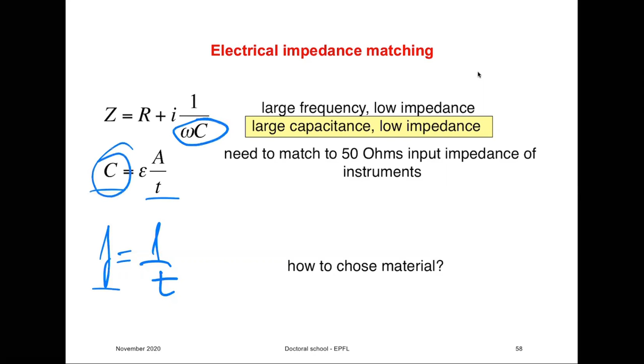This is the resonance frequency, close to this minimum point. And you want your transducer that operates at these frequencies to have an impedance which is as close as possible to 50 ohms. Why is this so? Well, you want 50 ohms because that's the input impedance of most instruments that are processing signal. And as we said before, you will get maximum signal transmission, maximum power transmission, if the impedances of two instruments, of two objects, are matching. So we need to make this as close as possible to 50 ohms.